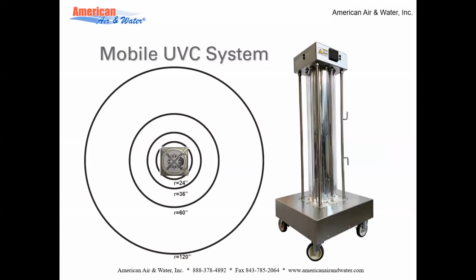This is an example of a mobile system. This is a 12-lamp system. It can disinfect a 400 square feet area in about 5 minutes, and it needs to move from point to point to minimize the shadow effect.